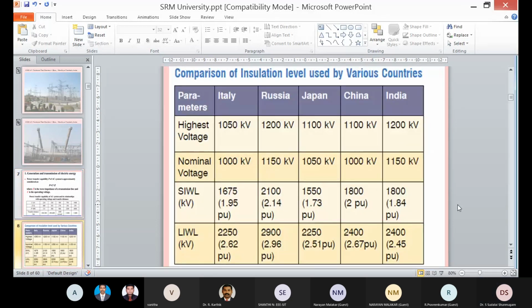Moving ahead. So right now, as Indians, we can be very proud. India has one of the highest system voltages in the world, 1200 kV. Our nominal or operating voltage will be around 1150 kV. We have selected a switching impulse withstand level of 1800 kV, and LIWL, the lightning impulse withstand level, of 2400 kV. We will cover that shortly. What is switching impulse level? What is lightning impulse level? Why should it be considered? And at which voltage do we have to consider it? Everything we will cover shortly.